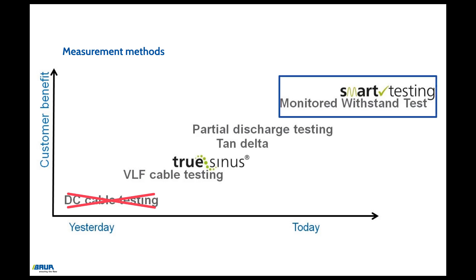In addition to cable testing, the monitored withstand test also includes a TAN-delta and/or partial discharge measurement and therefore provides more in-depth information about the condition of the cable. The current state-of-the-art permits a protective test with simultaneous diagnostics, plus a well-founded, predictive statement about the condition of the cable.